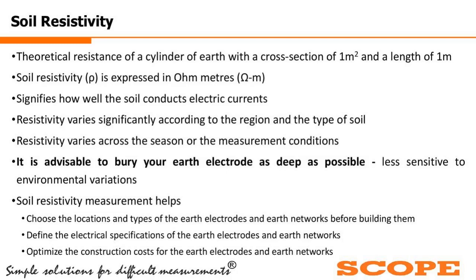Also, whether any special treatment is required for that specific soil, or we do not require any pre-treatment and only the normal thing is sufficient, or we need to put some special chemical so that we can have proper earthing. All those things come into the picture, and only then can we optimize the construction cost for the earth electrode and earth network. Because I can put in a lot of earthing electrodes and mesh, but how much do I need to invest, since we are using copper strips? How much copper strip? We have to optimize for any design. So the design cost optimization comes into the picture by doing the soil resistivity measurement.